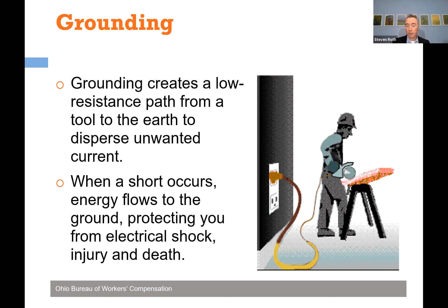So that's why something like this needs to be grounded, and it is. It has a grounding wire that connects to this metal casing. In the event that wire becomes frayed and touches the casing, it creates a pathway to ground and trips the breaker instantly, even before you pick it up. Some of you may have experienced this: you plug something in and the breaker trips right away. That means something in your tool short-circuited, tripping the breaker and protecting your life.